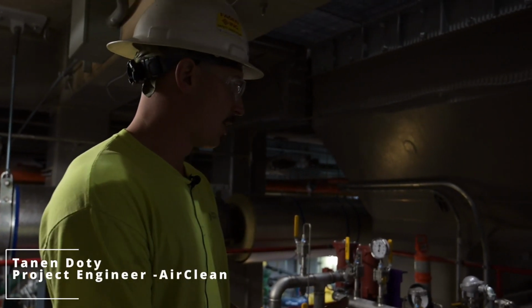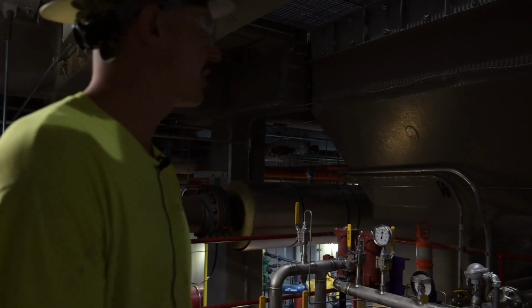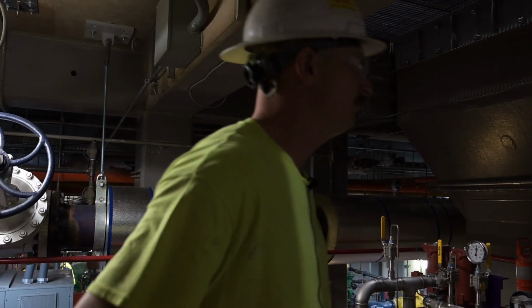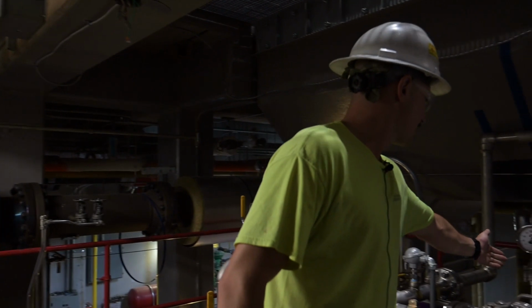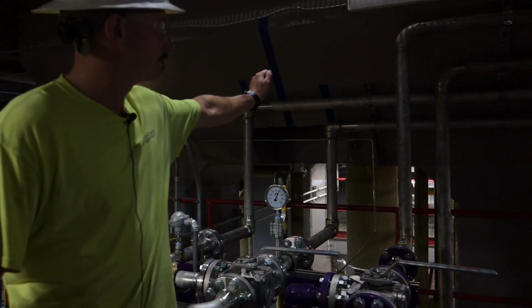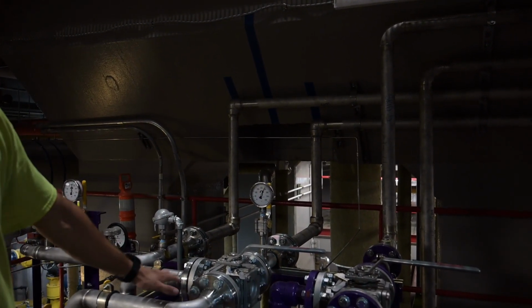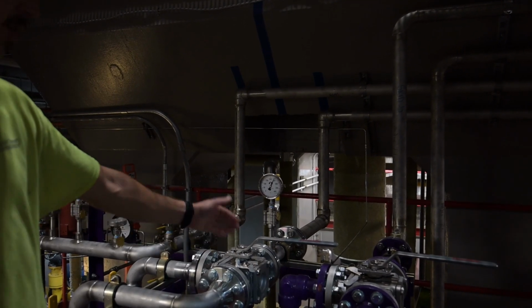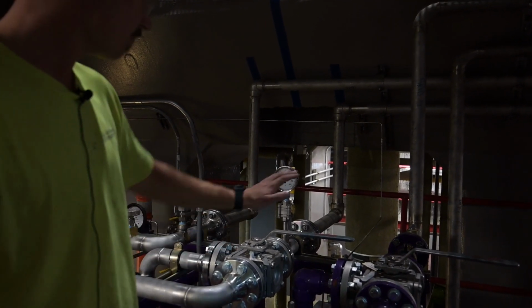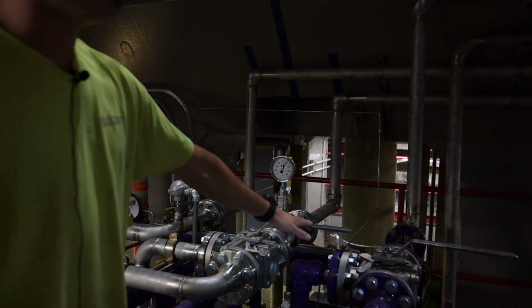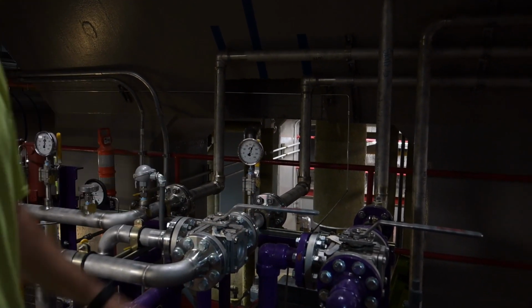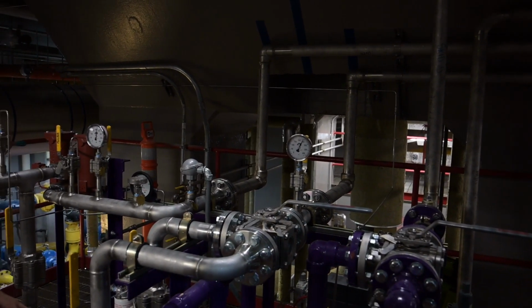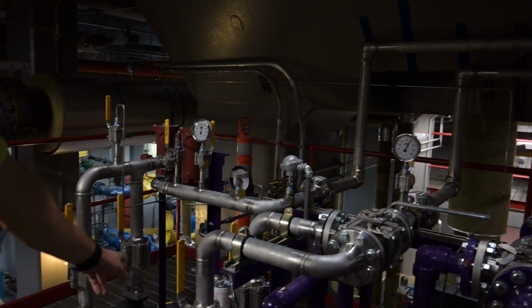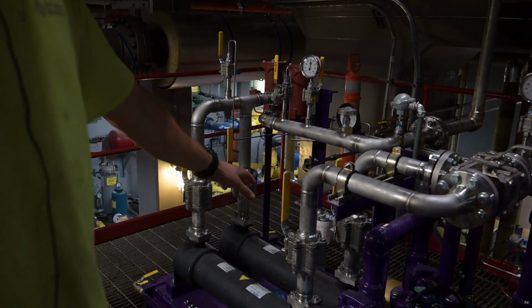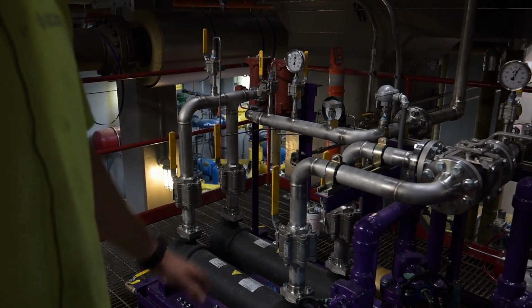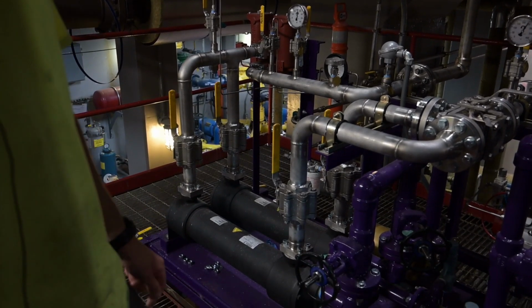All right, so we were down at the lube oil skid right below the turbine. This line right here is lube oil coming to the lube oil skid, so unfiltered oil coming into the lube oil skid. This is a three-way valve because we have duplicate heat exchangers. Each of them is 100% capacity, so you have basically an in-service spare.